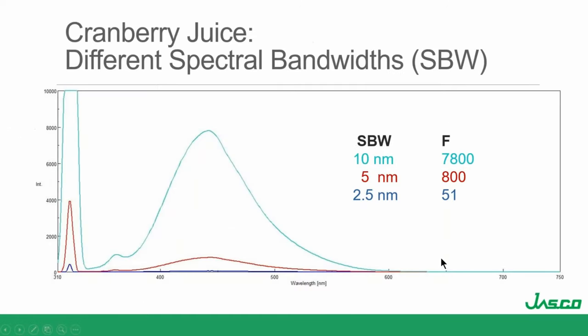Let's look at each of these and see what kind of impact it has on spectra. In this example with the cranberry juice solution, trying different bandwidths — 10, 5, and 2.5 nanometers — shows a huge difference in fluorescence signal. It's kind of hard to see any difference in resolution here, as anthocyanins in cranberry juice tend to produce a very broad, featureless spectrum.